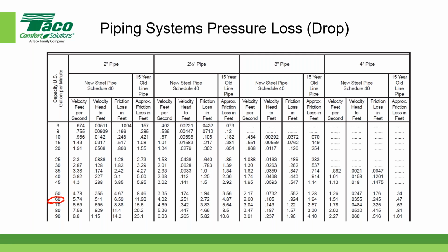And that 60 gallons per minute with a 2-inch pipe up here, Schedule 40 pipe, would have a velocity of 5.74 feet per second. And that's less than 8 feet per second, so that would work. But let's go over here to the pressure loss. Look at the pressure drop. It's 6.59 feet per 100 feet. But we said we wanted to have a maximum of 4 feet per 100 feet. So that 2-inch pipe is too small because it doesn't qualify for both of the categories. So let's go to the next size pipe, 2.5-inch. And again, we're roughly around 60 gallons per minute.